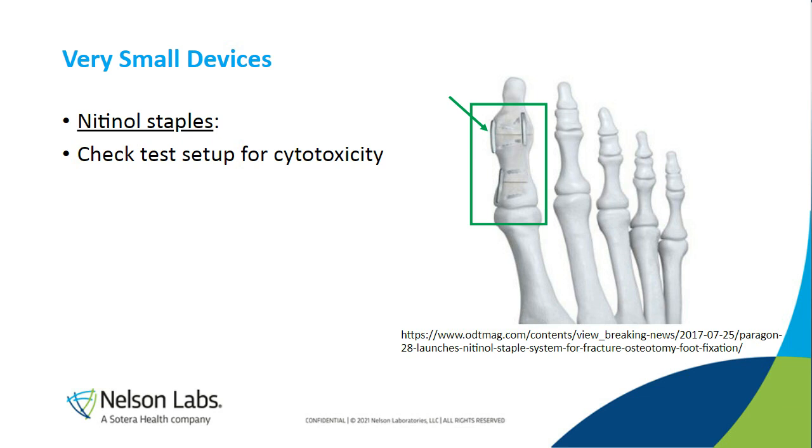So in this case, we would typically recommend having some additional data available to supplement the potential concerns from a patient perspective, right? And we always have to acknowledge that the depth of additional necessary data is, of course, dependent on the context and duration, right? In this case, because we have implantable devices and they will be there forever, I would recommend looking at metal release over time. For example, nitinol has nickel that might have leached out and caused this cytotoxic reaction when we have 1 million of them together in one pot. So what we want to know is, from a toxicity perspective, is there a concern? What we could do is pull the worst case amount and run chemistry for metals, maybe specifically nickel, to show that the nickel in this case, in a clinical use scenario, is not going to have any concern.